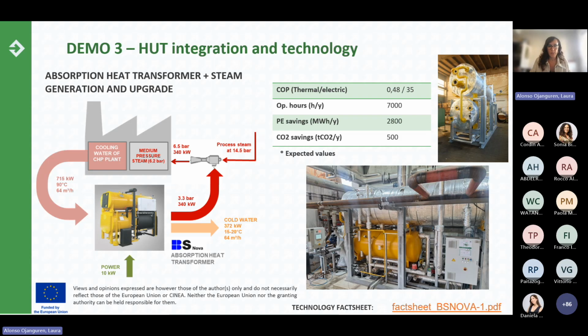Talking about some KPIs, when we talk about the efficiency of this system, normally in thermally driven heat pumps we talk about the thermal COP, and this means the power of upgraded heat at higher temperature level divided by the power of waste heat coming into the system. And this value is around 0.48.